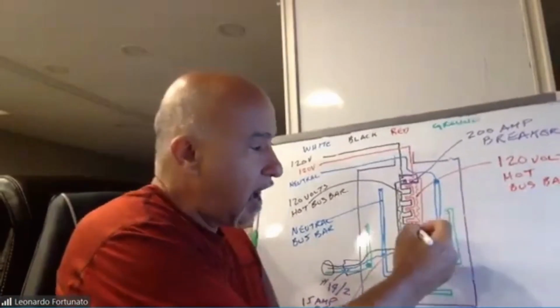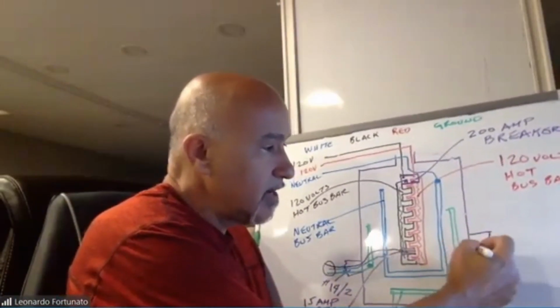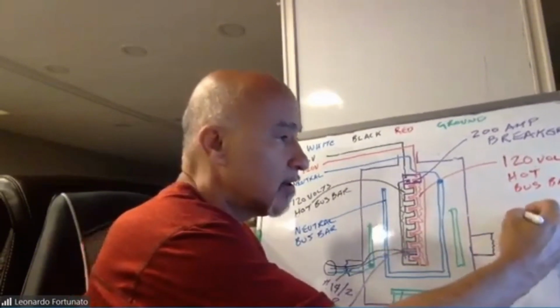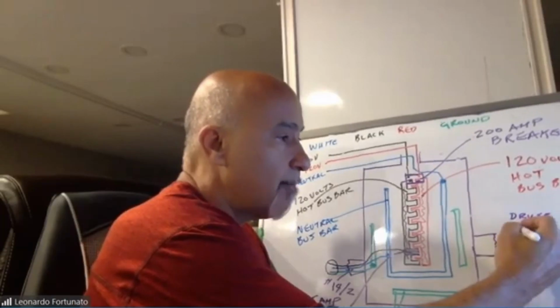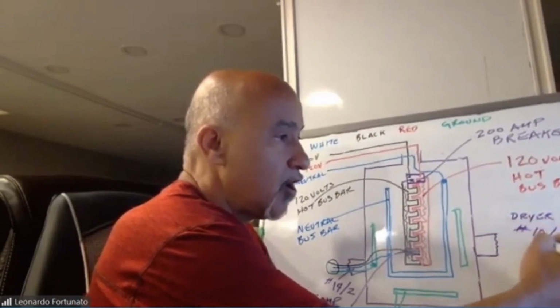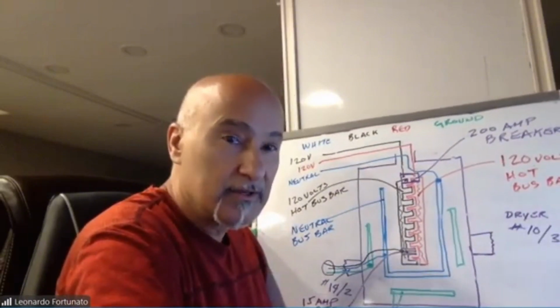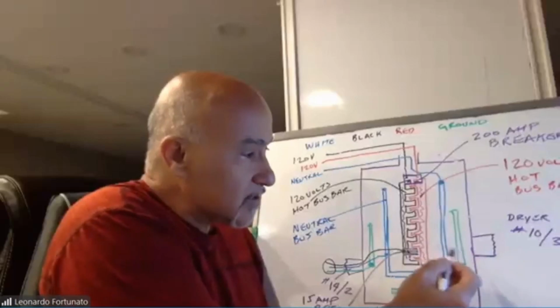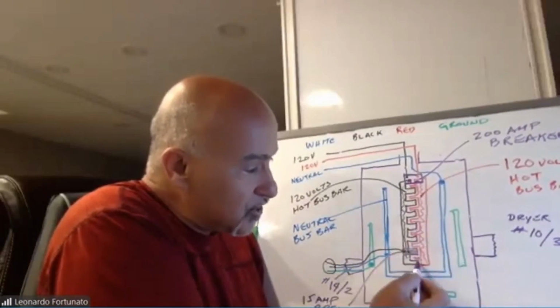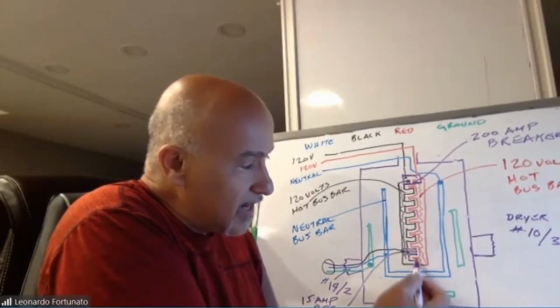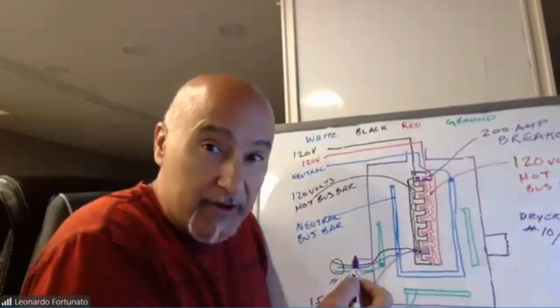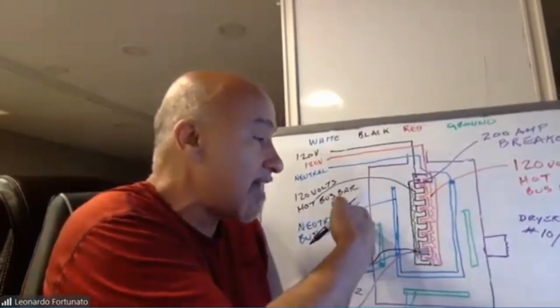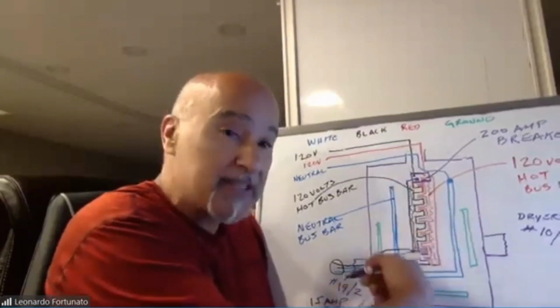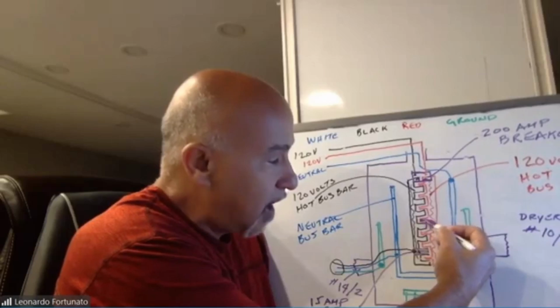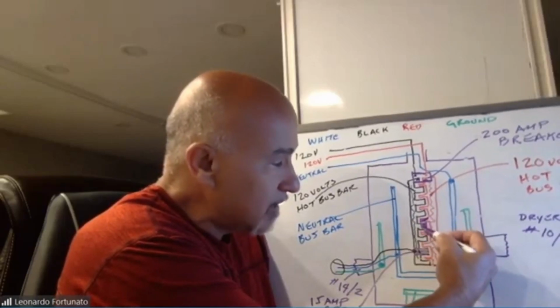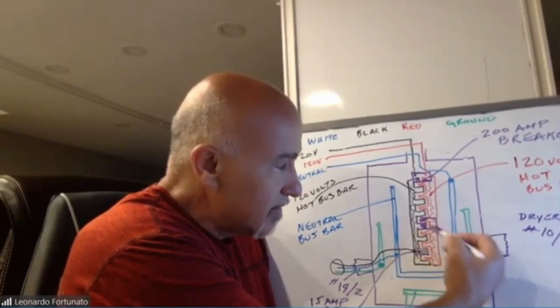Let's put the dryer on this side. I'm going to put a wire here. The wire I'm going to use for a dryer is going to be American wire gauge number 10, 3 conductors. If we now are going to connect this, we are going to put a breaker that sits, if you could see the hot bus bars in the middle, they stagger each other. You see how they're staggering each other? This allows me now to put breakers on this side and this side. And if I need to use both bus bars, I can. So now this breaker is going to sit on this bus bar and this bus bar simultaneously. You see that?